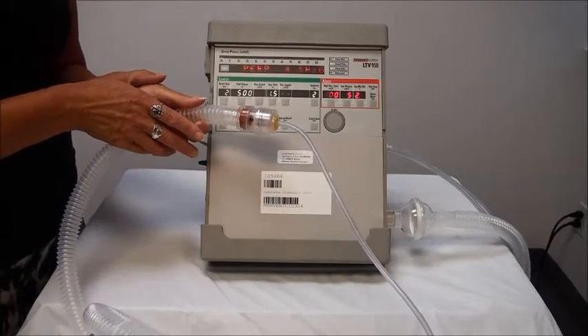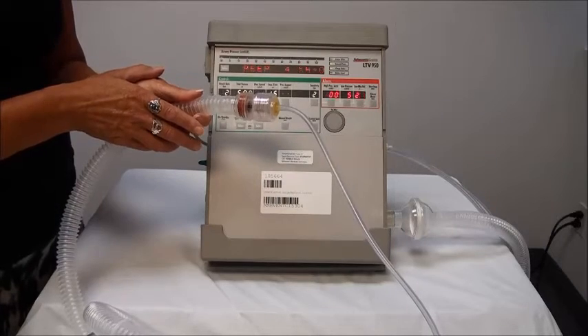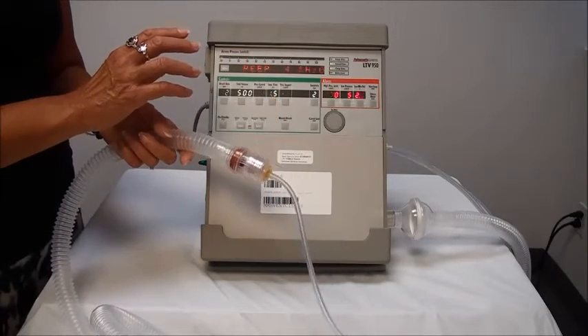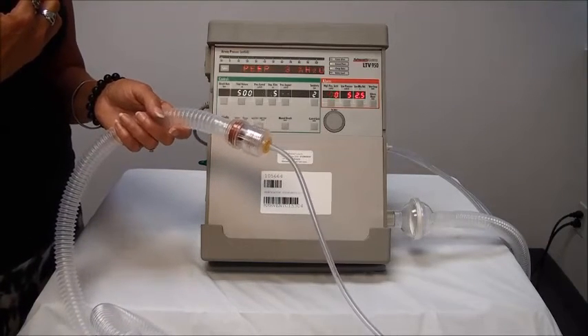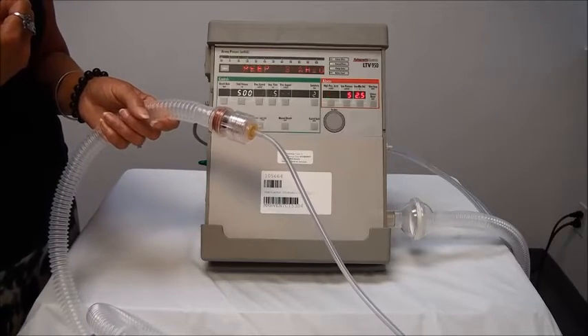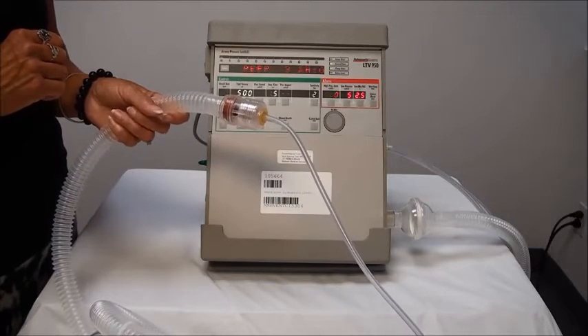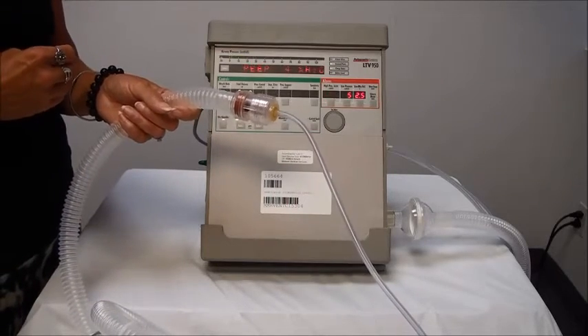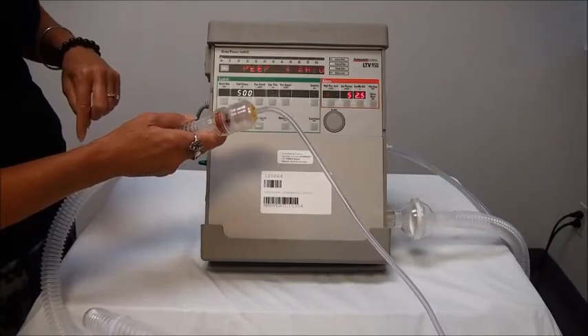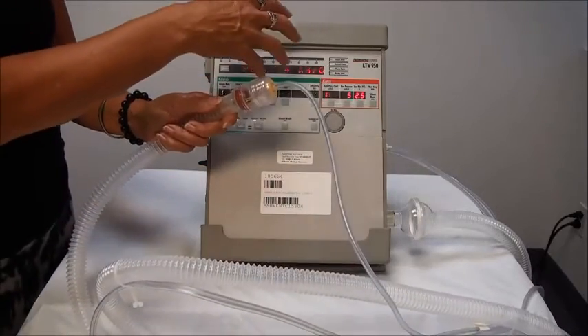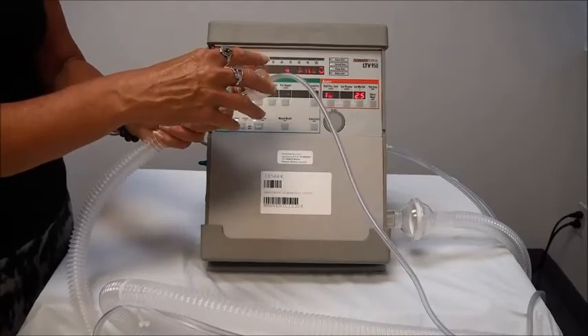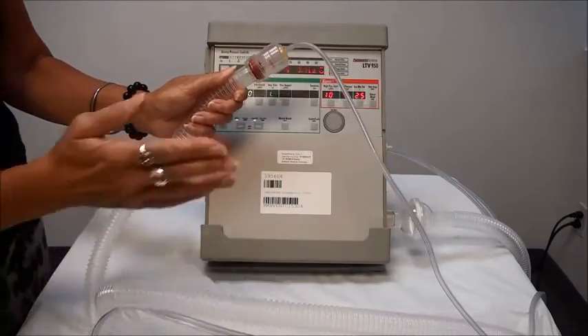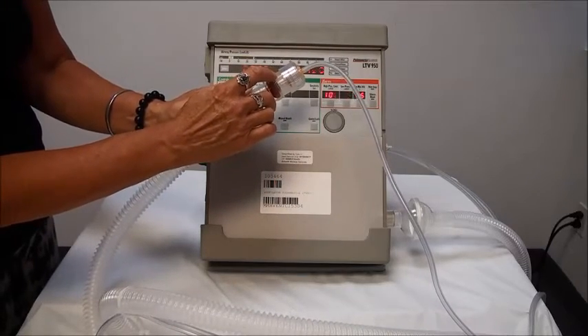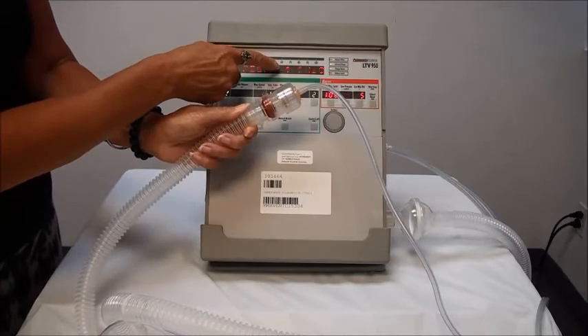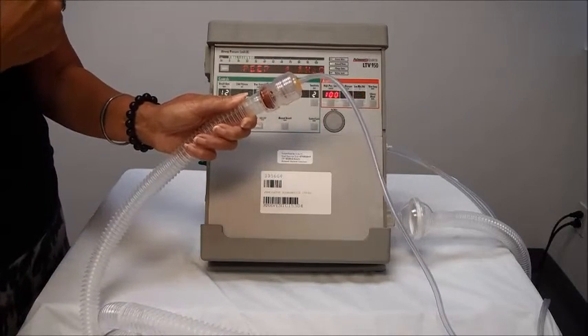So PEEP is positive end expiratory pressure, and what that does is when your patient's exhaling, you can set this at a pressure that will keep a slight amount of pressure in the lungs and will keep those airways in the lungs open a little bit down at the bottom of the lungs. So it helps prevent pneumonias and that sort of thing. So right now it's telling me that my PEEP is set at 4. This is the PEEP valve and it comes attached to the circuit. So there's no PEEP setting in the LTV 950 ventilator. The PEEP needs to be set on the circuit. And it's going to be very difficult to see, but there are some numbers on your PEEP valve that you can twist this to set at, but you always should be reading what it says on the ventilator to get a more accurate setting.